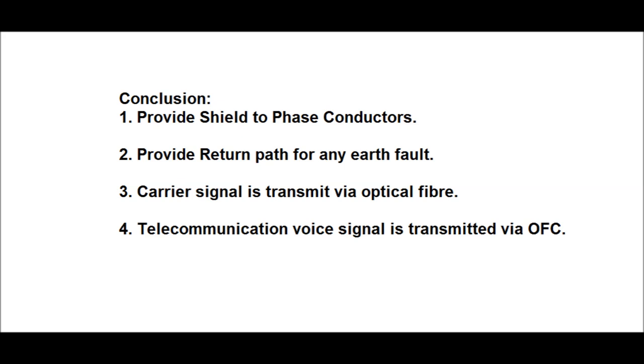In conclusion: number one, the earth wire provides shielding to the phase conductors of the transmission line. Number two, if the horizontal span between phase-to-phase conductors is more, instead of one earth wire, two earth wires are used — mainly at voltages above 400 kV. Number three, it provides the return path for any phase-to-earth fault in the transmission line. Number four, carrier signals are transmitted via optical fiber. Number five, apart from carrier signal transmission, it provides telecom communication and voice signal transmission via OFC — optical fiber cable.